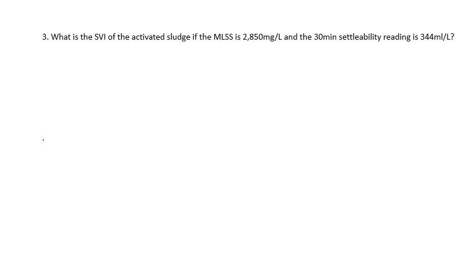What is the SVI of the activated sludge if the MLSS is 2850 milligrams per liter and the 30-minute settleability reading is 344 milliliters per liter? Get your knowns and unknowns out of the question: 2850 mg/L and 344 mL/L, and we're looking again for the SVI.